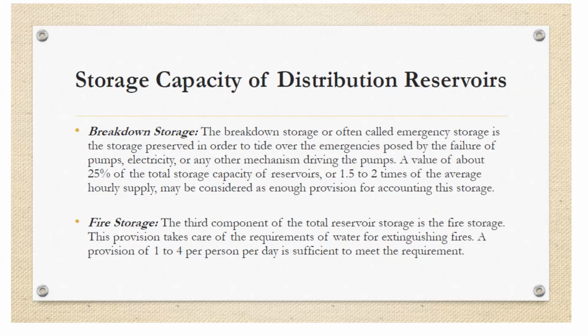This provision takes care of requirements of water for extinguishing fires. A provision of 1 to 4 liter per person per day is sufficient to meet the requirement. Per head per day against 1 to 4 liter capacity we must keep ready against the fire storage.